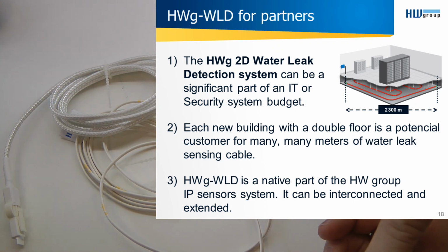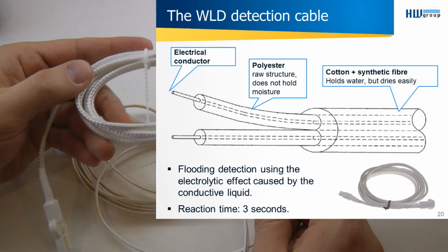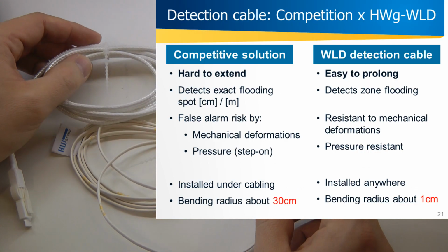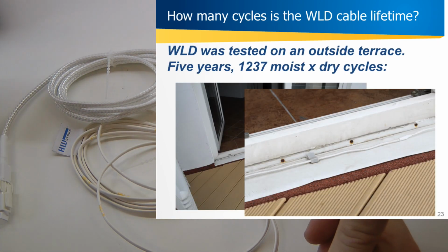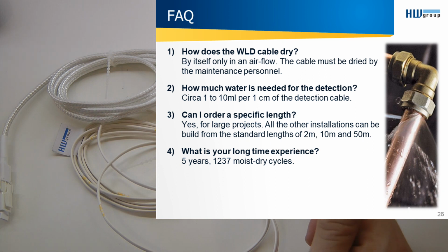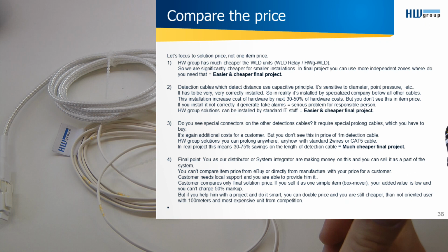For commercial and industrial applications, what is also really important is that the detection is reliable, because in most cases these sensors are hidden out of sight. If I take the server room example, that would be under the raised flooring. So if you have an alarm and you need to inspect it, it's probably going to be a very labor-intensive process. You definitely need a reliable system, because as soon as you get false alarms, the alarm system is just going to be turned off, and basically it's going to be useless.